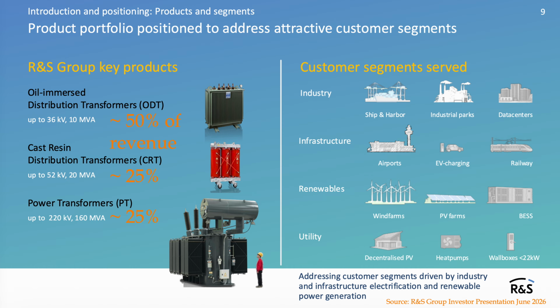R&S Group have the whole product range of transformers except the very largest, and they serve a broad range of customers. Oil immersed transformers use oil for insulation and to carry away heat. They are the cheap, durable workhorses, and the oil cooling lets them run hot and absorb overloads.